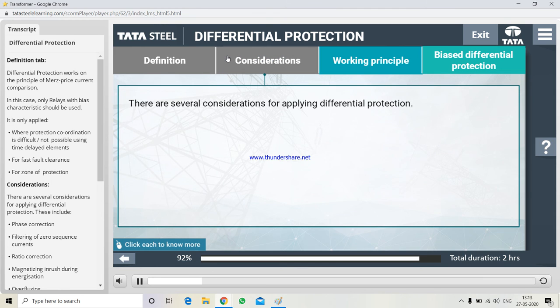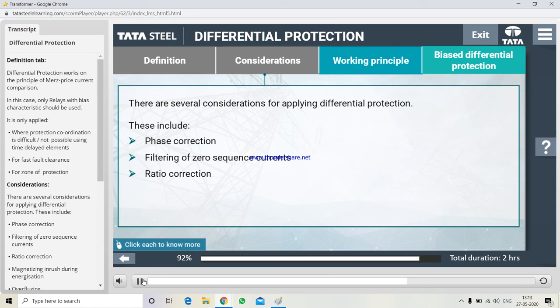There are several considerations for applying differential protection. These include phase correction, filtering of zero sequence currents, ratio correction, magnetizing inrush during energization, overfluxing.